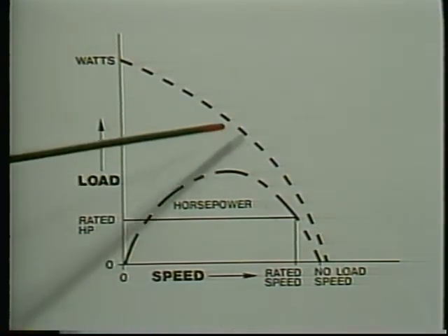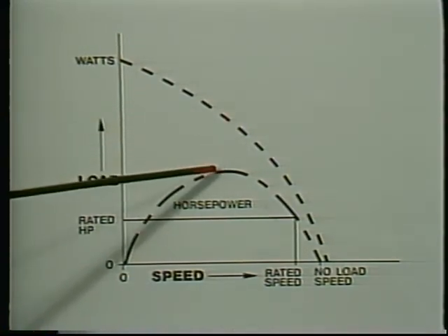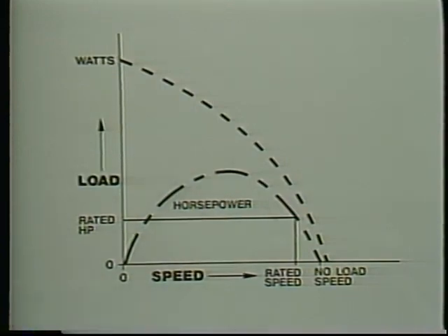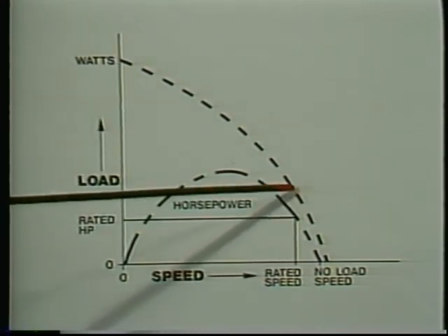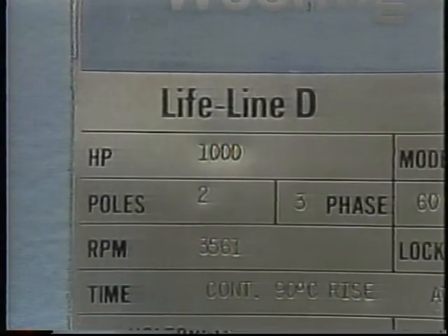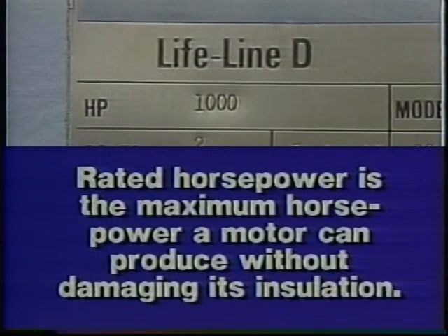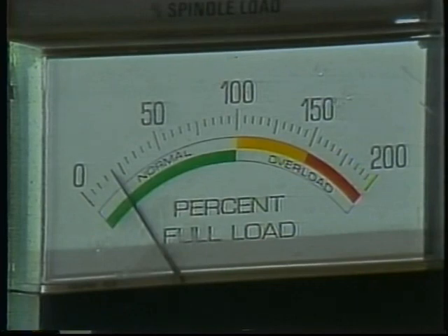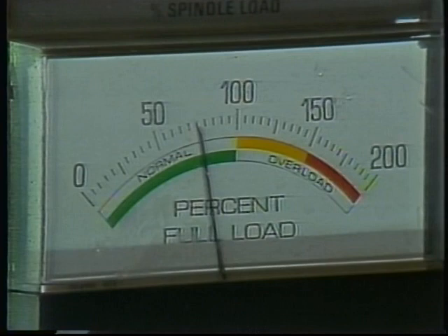Operating under heavy loads at low speed is almost as bad. At maximum power, the efficiency is low, but the difference between watts in and horsepower out is still large, and a motor will heat up if operated under these conditions for very long. At rated horsepower, a motor will heat up comparatively little — this is what rated horsepower means: the maximum horsepower a motor can produce without heating up so much that the insulation inside is likely to be damaged.